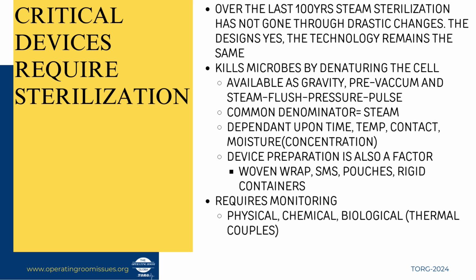Again, because of our critical devices requiring sterilization, okay, sterilization over the last 100 years has not changed. Steam sterilization is still the sterilization choice, okay? It's reliable, it's cheap, and it doesn't leave any residue on your devices. And it's very effective if utilized correctly and maintained properly. Okay? It kills microorganisms by denaturing the cell. Okay? The common denominator on all of our sterilizers, depending on what type it is, whether it be pre-vacuum, gravity, IUSS, or tabletop, is that it uses steam. Okay? At a certain moisture, certain time, temperature, and contact is critical.